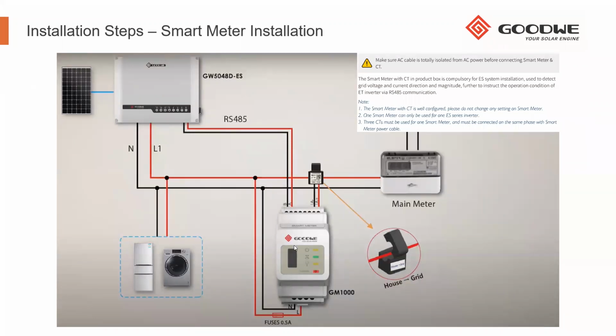The smart meter is very important to get the best out of your system, so make sure that it is properly installed. If the smart meter is not communicating correctly or is not properly connected, you might get unexpected conditions on your inverter, like it not discharging the batteries at all in self-consumption. If your CT is in the wrong direction, the inverter also will not discharge the batteries for self-consumption because it is reading export. And should it read export, it will then make sure that the batteries are full.